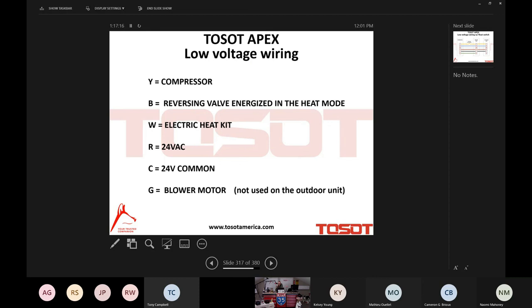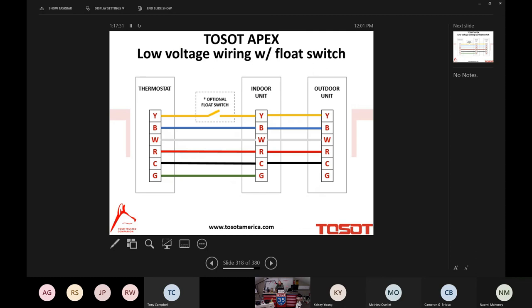Y being our compressor, B being the reversing valve, remember, energized in the heating mode. W is the electric kit, if we're utilizing it. R, 24 volt. C, 24 volt common. And G is our signal for the blower motor indoor unit to operate.